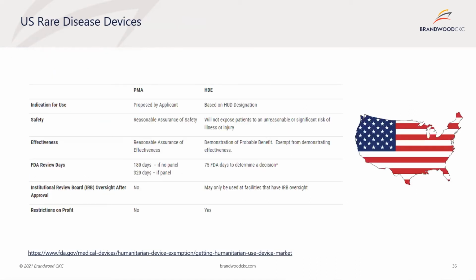So if we compare the difference between a PMA and an HDE, the indication of use is proposed by the applicant with the PMA, and the HDE is based on the HUD designation. The safety needs to have a reasonable assurance for the PMA. And here's where we see the difference. It will not expose patients to an unreasonable significant risk for illness or injury. On the effectiveness side, of course, a PMA will require a clinical trial. And here's what we're talking about. For the HDE, there has to be a demonstration of probable benefit. And there's an exemption for demonstrating effectiveness for the approval. The FDA review timeline is significantly smaller. There are restrictions for profit, and the product can only be used under IRB approval.